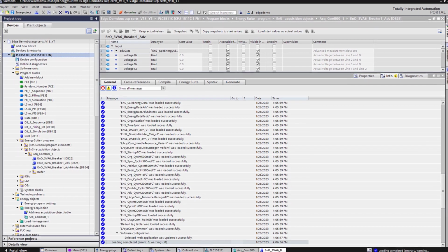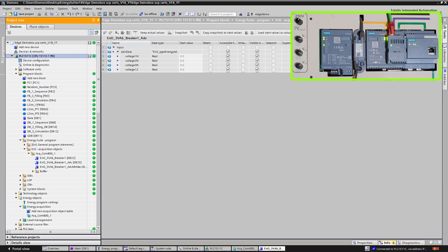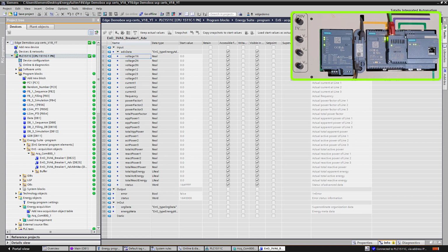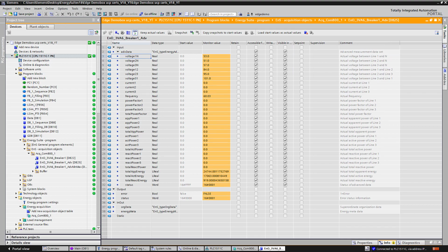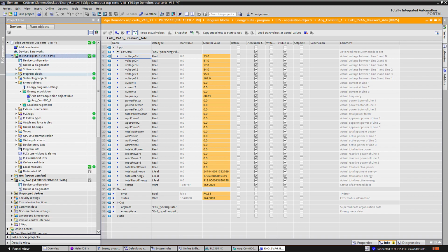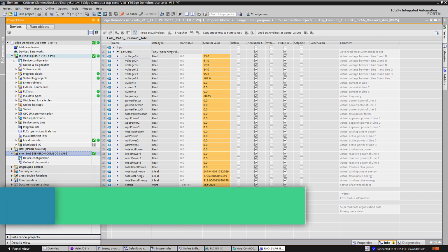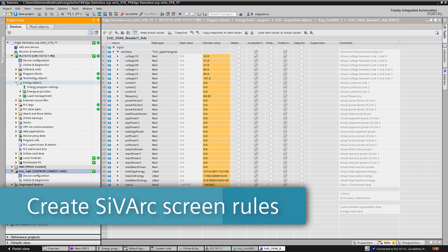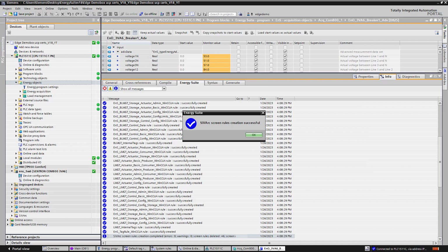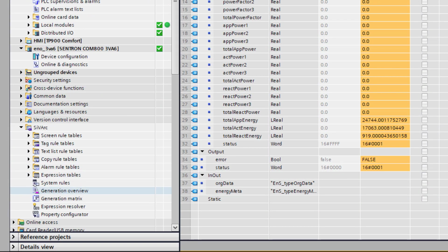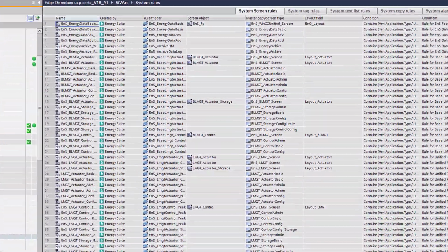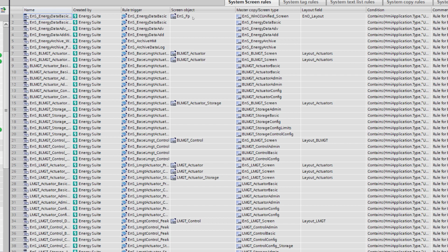Once we load, we go online. Quickly, you can see the Profinet expansion module went green. And here's some of our data. You can see there are totalized values down at the bottom. Next, it's time to work with SiVArc, which is our way of automating the HMI visualization. Those screen rules are placed inside of the appropriate folder down at the bottom of the project tree. Screen rules help us define rule triggers that are based on function blocks, which also help us to guide objects from the library to be placed into specified screen windows inside of our runtime.